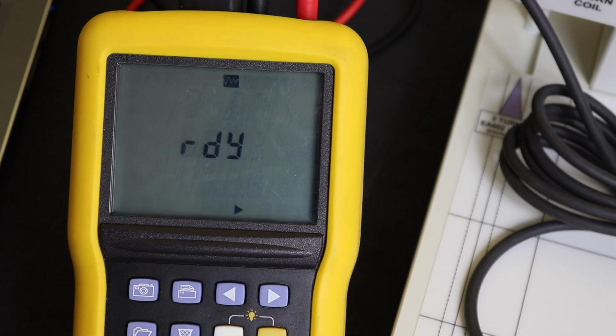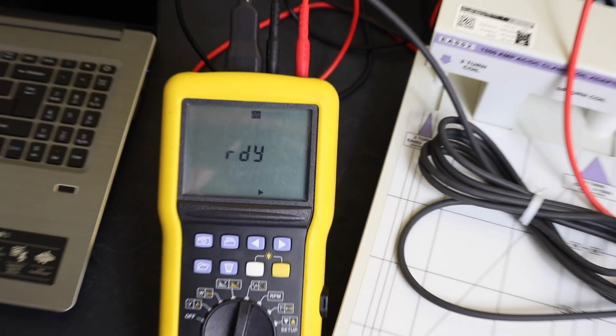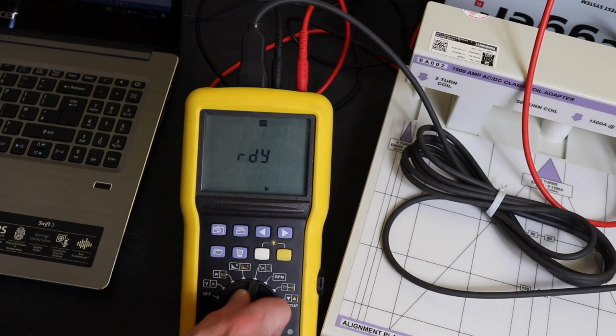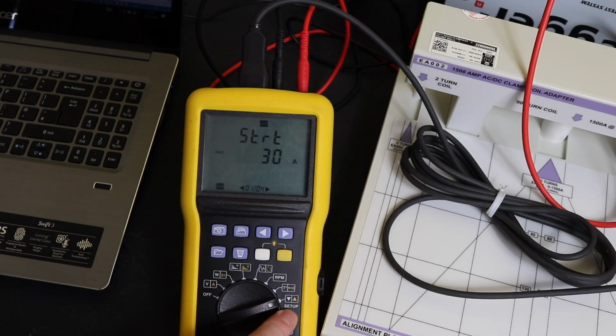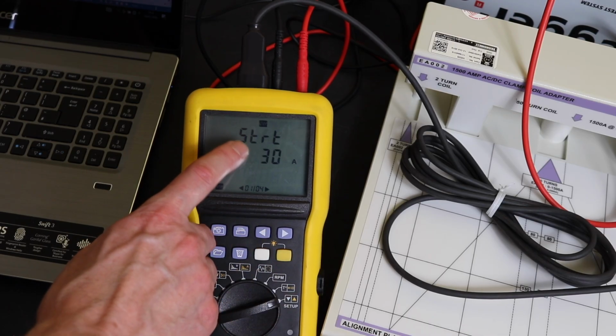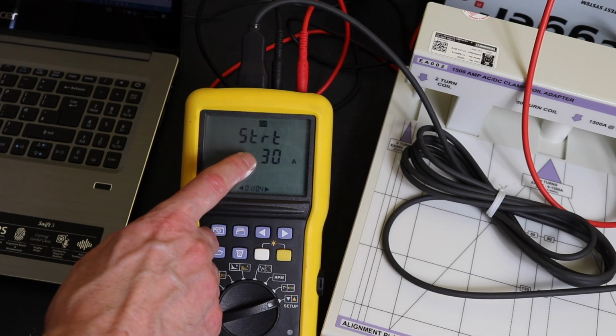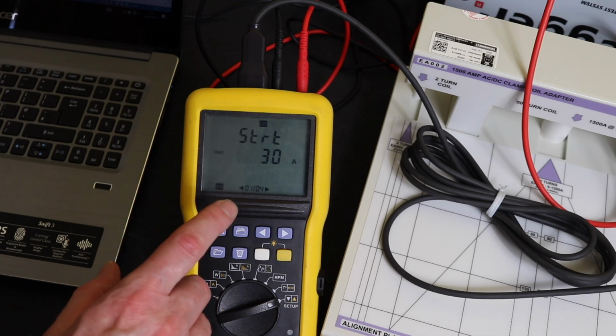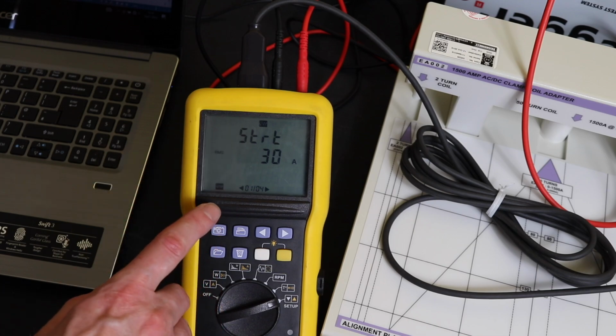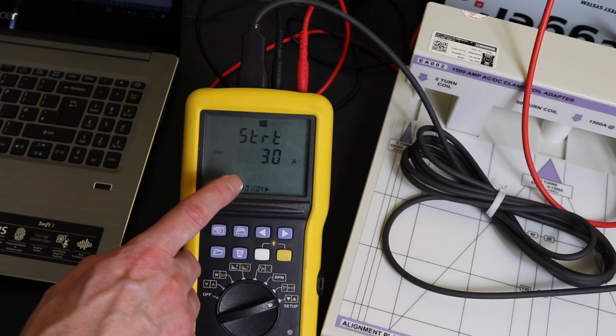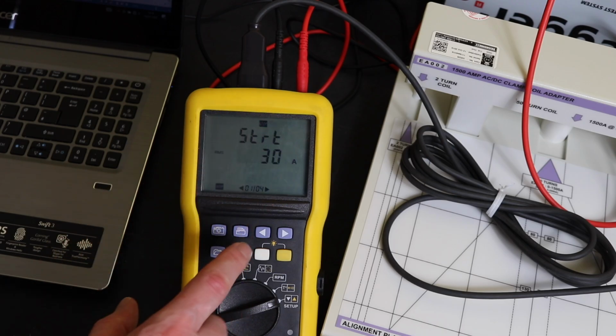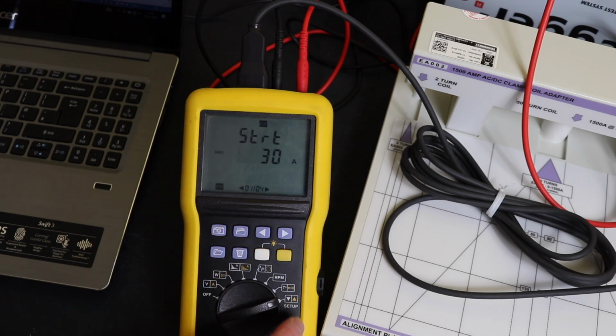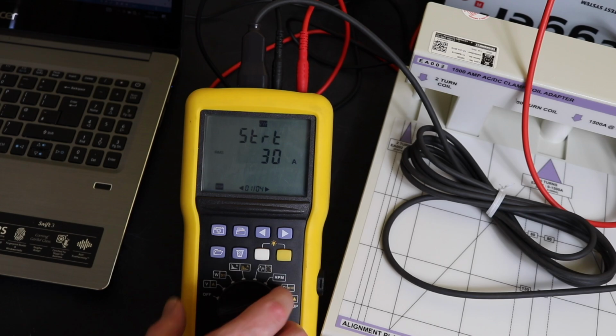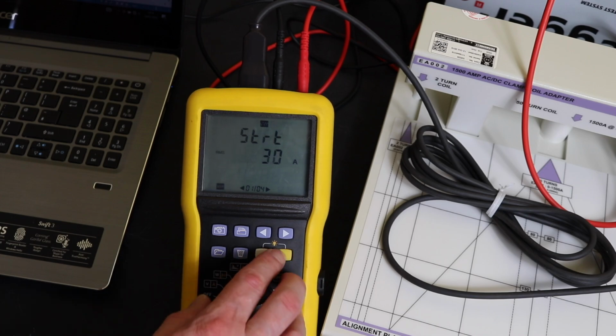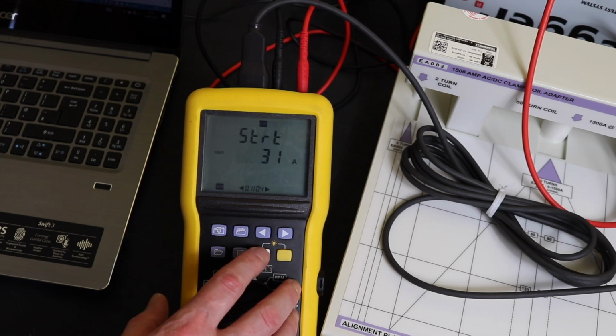We switch to ready. What I'm just going to do, if we just boom out, down here there's a setup function here. So on our setup, we set up our starting current, that it initializes it. That's quite unusual. The vast majority of the current clamps, in fact all the current clamps that I have that have an Inrush function, you can't set the threshold, but you can on this instrument, which is an advantage. So you set that up using the yellow and white buttons there.